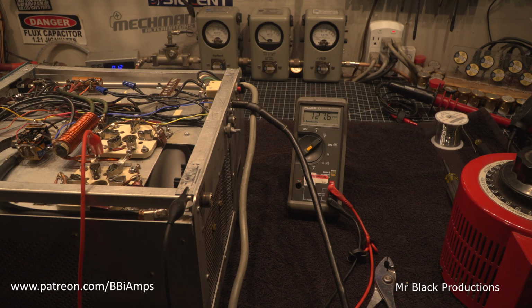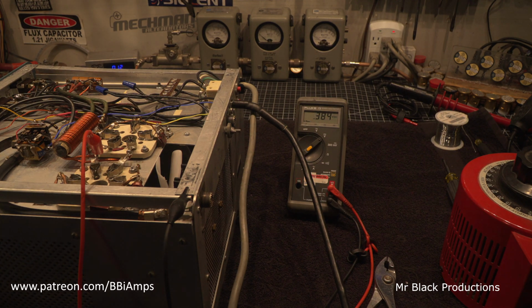Very simple. Okay. Shut this down up here on the front. And I know for a fact that this amp is going to work now that we've fixed the high voltage, fixed the filtering bank, fixed this breaker, and fixed the keying circuit. Got all the bugs worked out of it now.